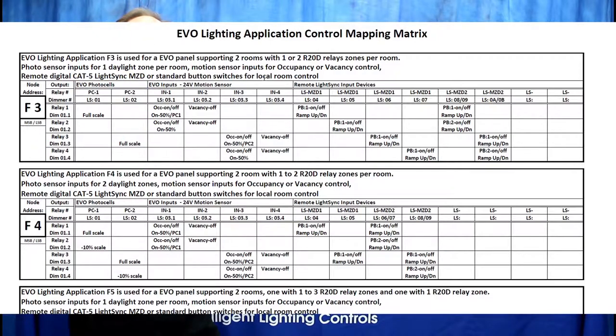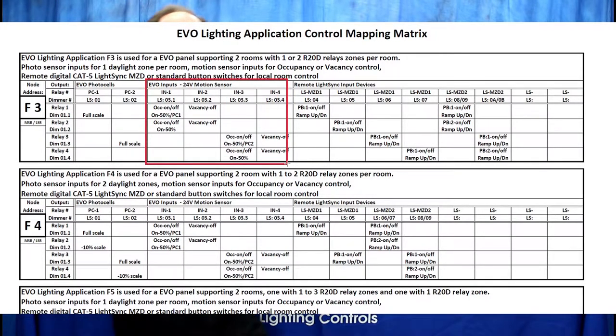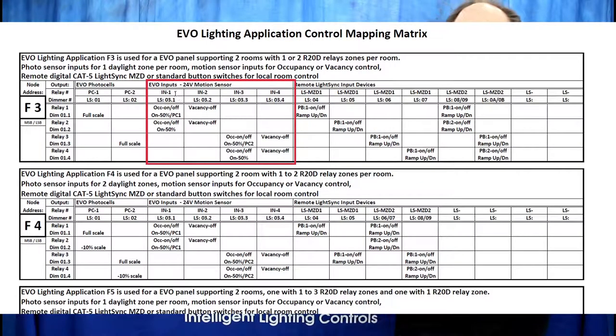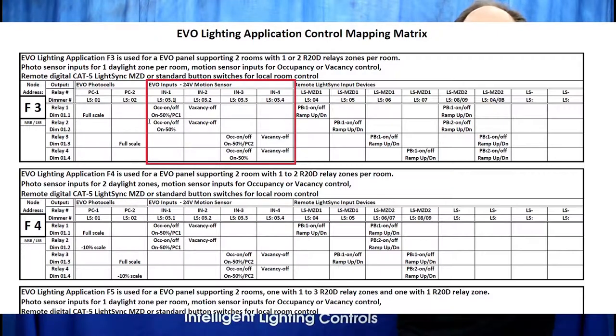The next section shows the four occupancy sensor inputs and the associated control of relays or dimmers. Input 1 will operate relays 1 and 2 on and off with a dimmer setting of 50% at the on command of the motion sensor.